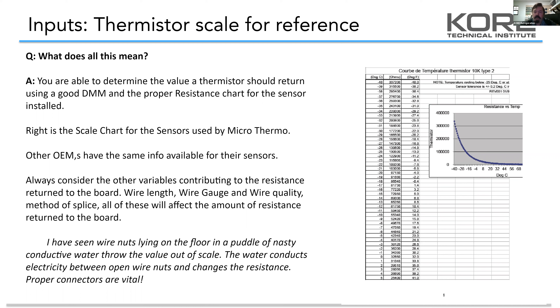In the field, you're not always going to have a scenario where it's so blatantly off that it's obvious which item is bad. Generally, you don't have to get very deep — you're going to know very quickly if the reading is wrong by disconnecting the wire. If you do pull your wire off and get any sort of temperature reading other than fully open or minus 58 — or whatever your control system indicates for a full resistance coil — then you know your board is reading something it shouldn't if there are no wires there.